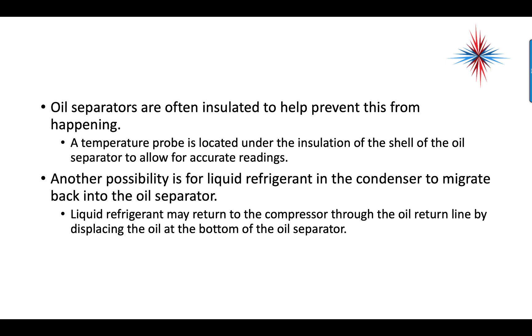A temperature probe is located under the insulation of the shell of an oil separator to allow for accurate readings. Another possibility is for liquid refrigerant in the condenser to migrate back to the oil separator. Liquid refrigerant may return to the compressor through the oil line by displacing the oil at the bottom of the oil separator.